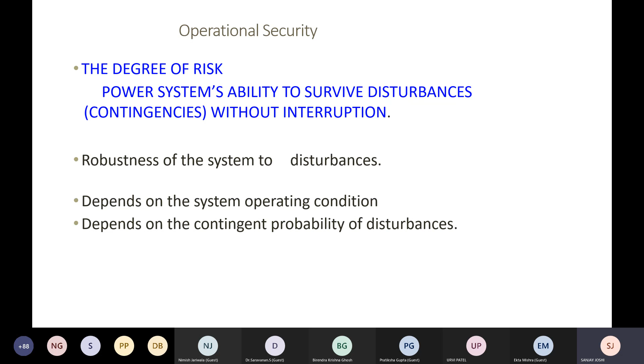How do we ensure operational security? Real-time monitoring of transmission line flows ensures they are not overloaded. Contingency analysis is done to check what happens if something occurs to the grid situation, and we ensure the system remains secure. Corrective and preventive action ensures that if a contingency occurs, it does not create a system breakdown. This contingency analysis is repeated periodically. The load and generation balance and frequency stability are required to be kept within the permissible band of 49.7 to 50.2 hertz, that is 0.5 hertz.